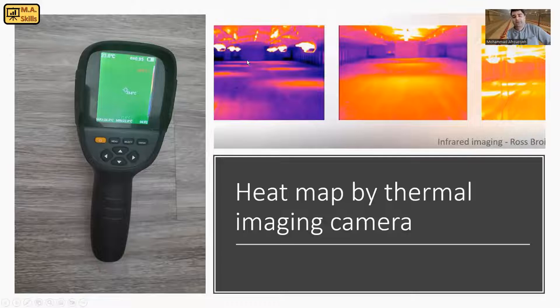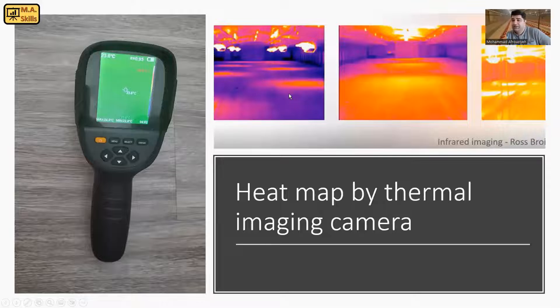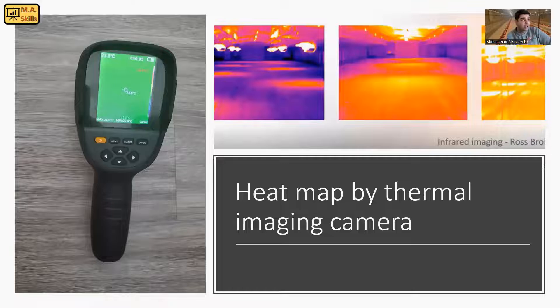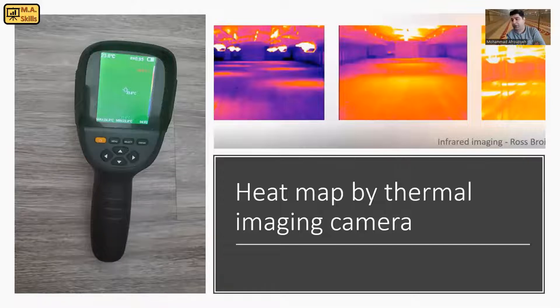For example, in the left image you can see radiant heaters being used, and just underneath the heaters are warm but other places are cold. In the middle or right picture, you can see the heat is distributed evenly through the barn. It's really important — when we talk about temperature, we're not just talking about air temperature. We need to pay attention to the litter temperature and also to the heat map to see how heat is distributed around the barn.